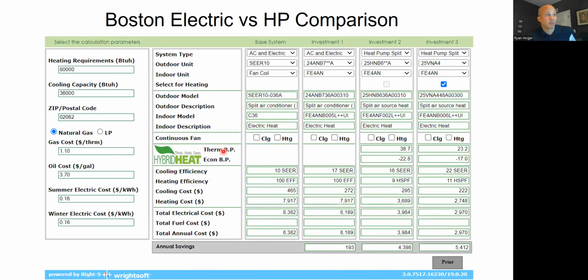In any case, thermal balance point for this particular model of heat pump, which is a 16 SEER 9 HSPF 2-stage heat pump, was 38. Economic was negative 22. That means at 38 degrees and below, that model of heat pump cannot make enough heat for this building, and I need to switch over, or in this case, all electric, I need to add on electric heat. Economically, if I get down to negative 22, that's when I get below 1.0 COP on the heat pump, and it would be cheaper to turn the heat pump off and run the all electric. It's probably never getting to negative 22, so I'm probably never even going to have to think about that.